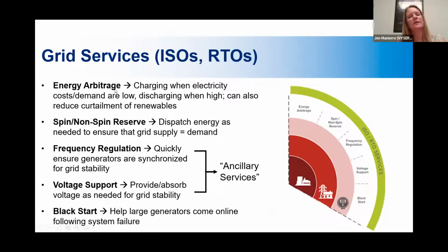Energy arbitrage. I talked about this, I hinted at it a little bit a couple slides ago, but it's basically charging when electricity costs or demands are low and then discharging when it's high. This can also reduce curtailment of renewables, which is basically sometimes you have to scale back a solar system because there's too much electricity already on the grid. It doesn't have the capacity to accept all of the energy that system is creating when it's really sunny out. So that system can have an on-site battery, for example, that the PV system charges until the grid can handle that additional electricity going in.